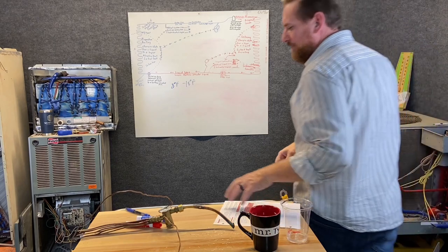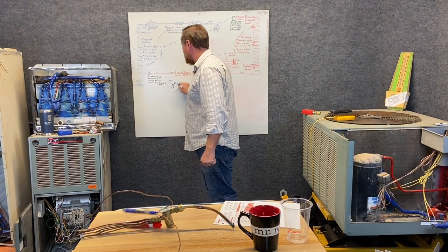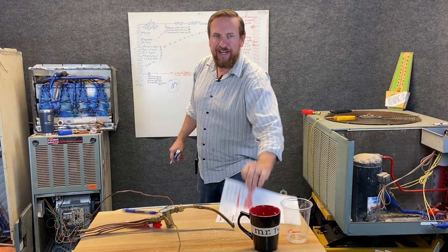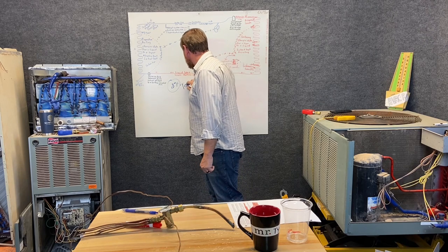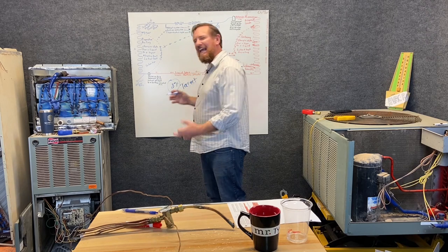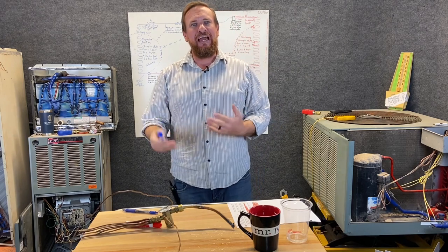That makes it very easy for us. They want an 8 degree superheat. So we know that our target for this manufacturer of this brand, which I won't say who it is, they want an 8 degree Fahrenheit target superheat. That's target, what we want to be at, what we're aiming for, the speed limit if you will. Now we need to look and see what we're actually getting.